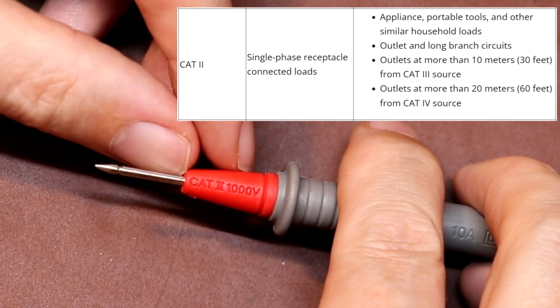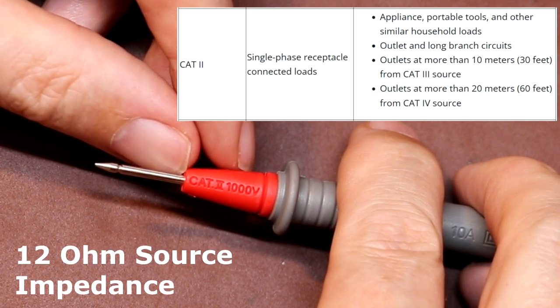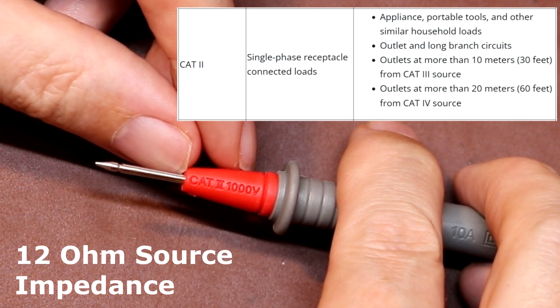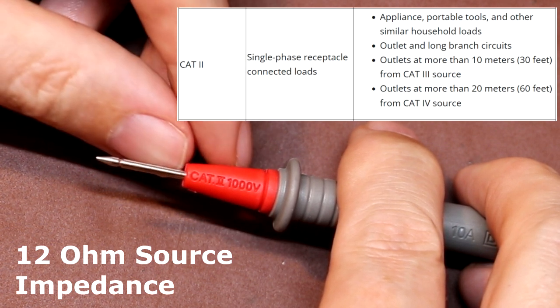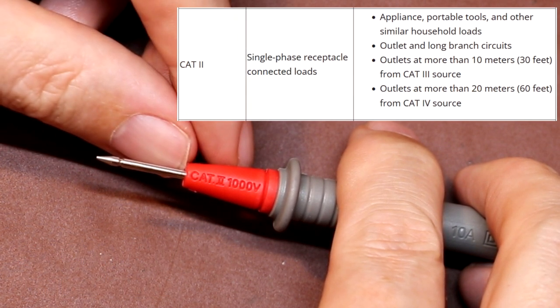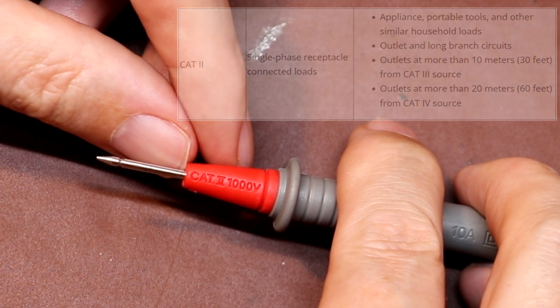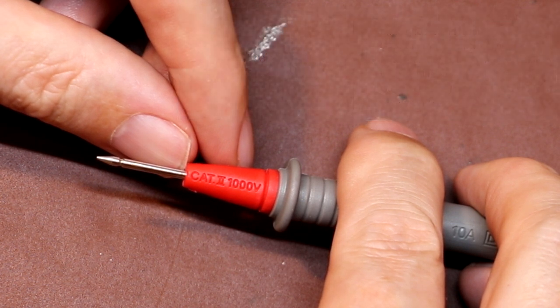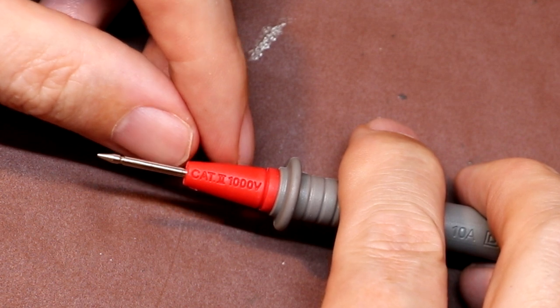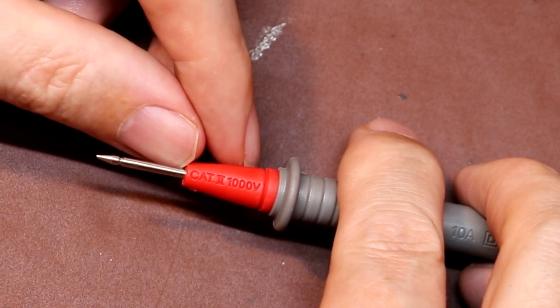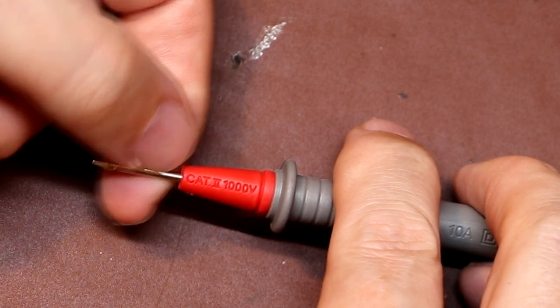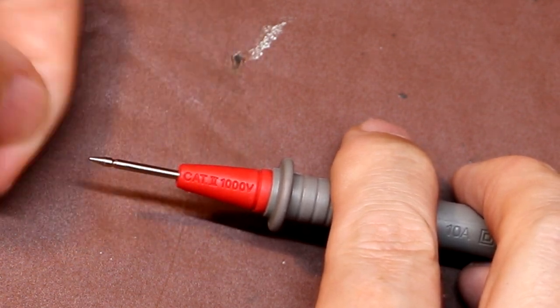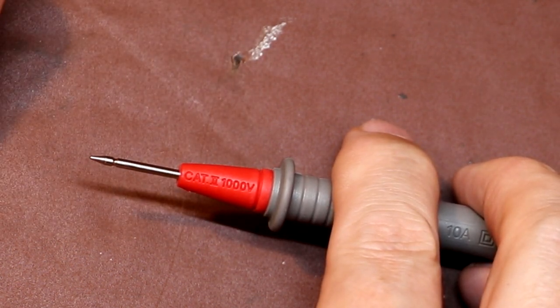But what the category 2 part is telling us is the maximum energy within the circuit that we can actually measure with these probes. Because if you're not careful, if you were to short something out, you could get a very large flash and a bang. And in fact, the flash and the bang could be so big that it could seriously injure you. So the reason that these have got a low category 2 rating is because we've got all this exposed metalwork which could short out when you're poking around inside a panel.